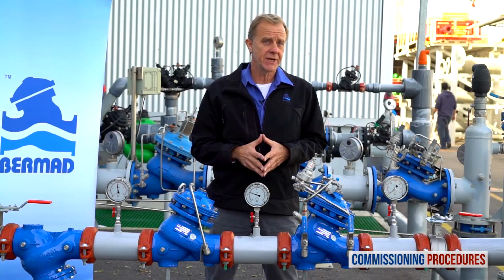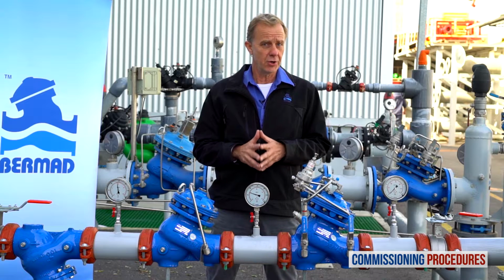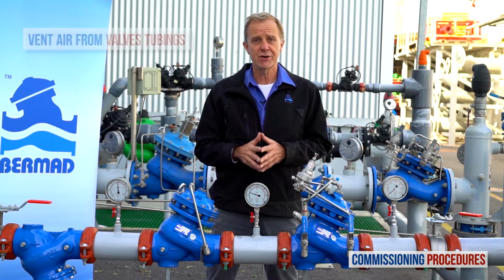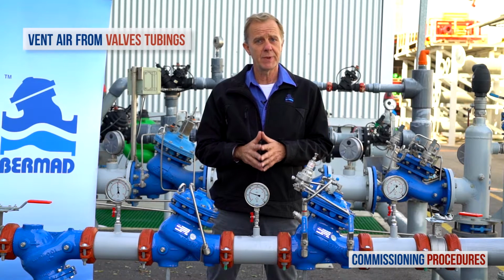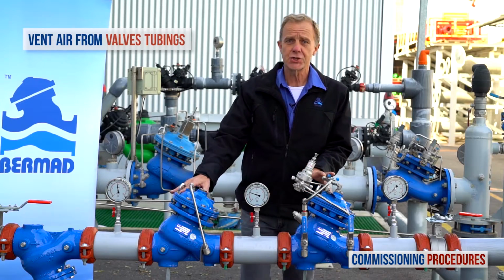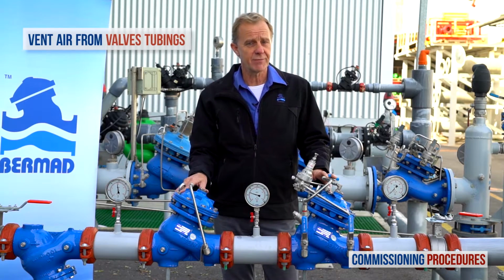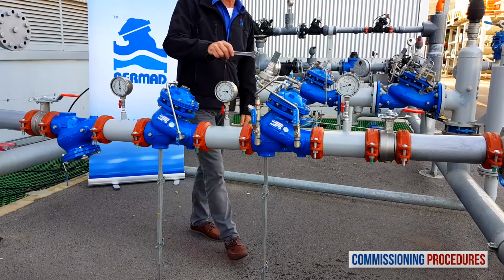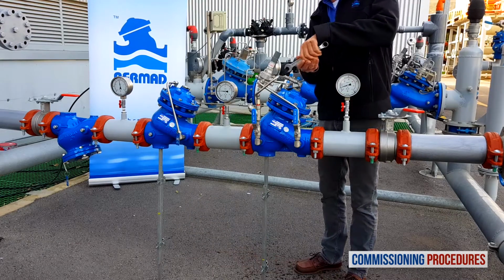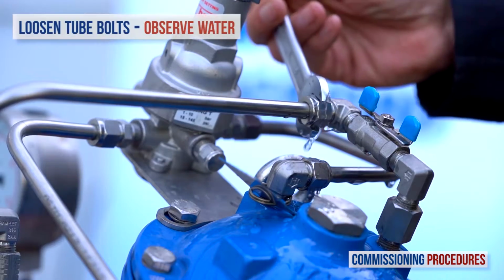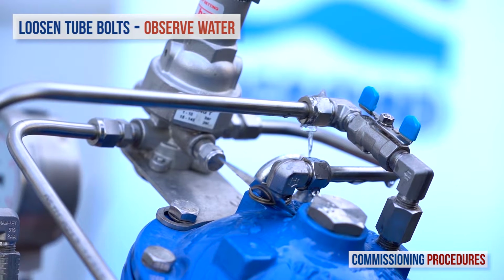The final stage in the commissioning process, whether or not you performed recalibration, is to remove any residual air from the pressure reducing valves. This ensures a more stable and positive pressure control. To vent air from the secondary valve's control loop, loosen the tube eyebolt attached to the valve cover at the highest point of the valve's control chamber.